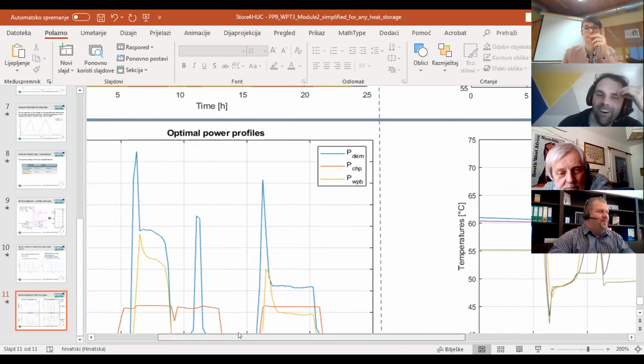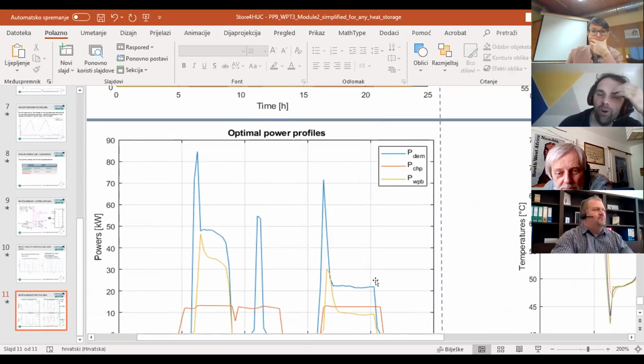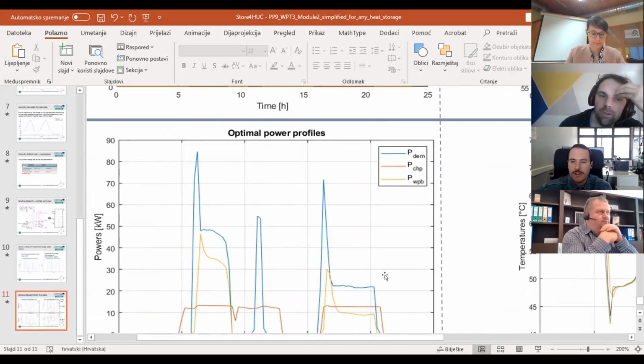Yes, Milenko, you are correct. Well, Philip will know better. Philip, did we take into account the tariffing of electricity here? Yes, we did. During the night, the price of running the CHP is positive, because the price of the electricity is lower. That's why at the beginning of the day, while it's still night, you see the temperatures are still around 60, which is the low.